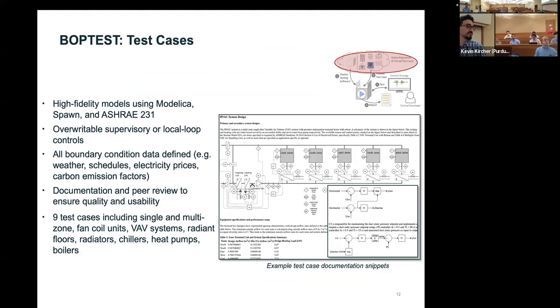Starting with the test cases, as I mentioned, they are high fidelity models using Modelica or Spawn, and in some of them we also use the recently released ASHRAE 231 for control sequences. So ideally, in a little bit, you could go from the virtual building, the virtual deployment and testing, to translating those control sequences into actual BAS control sequences that then go into the real building. And because of the level of detail in the modeling of the HVAC and the control, it's possible to overwrite the supervisory layer, like set points, or the local loop controls. If you want to control the pressure set point differential on an air handling unit, you can do that.